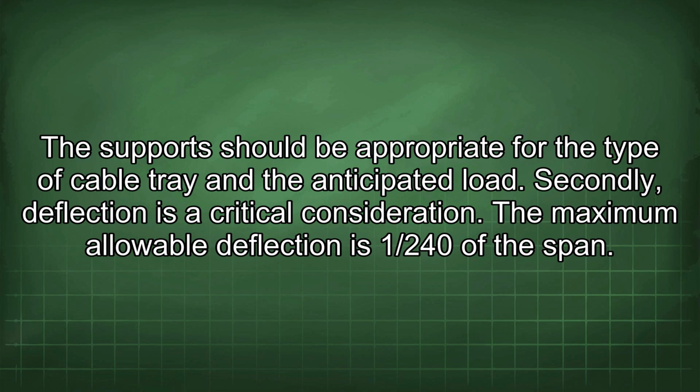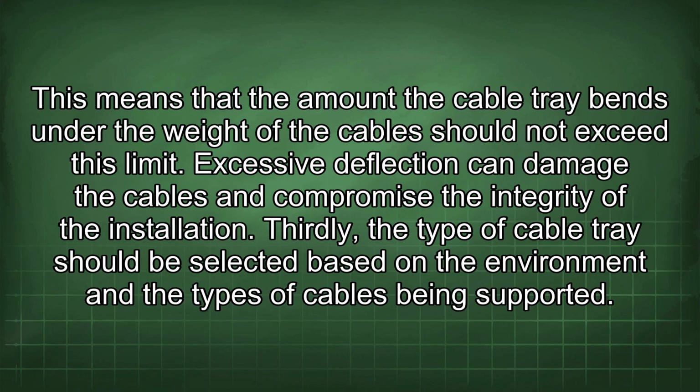Secondly, deflection is a critical consideration. The maximum allowable deflection is 1/240 of the span. This means that the amount the cable tray bends under the weight of the cable should not exceed this limit. Excessive deflection can damage the cables and compromise the integrity of the installation.